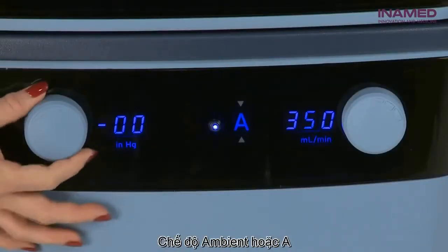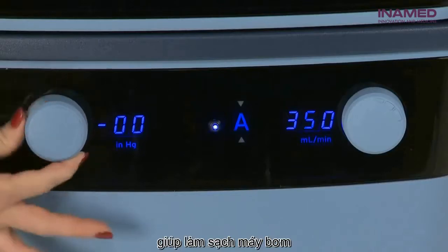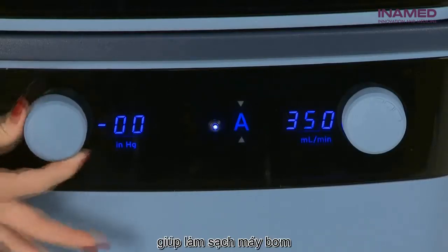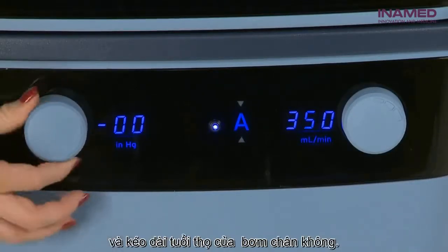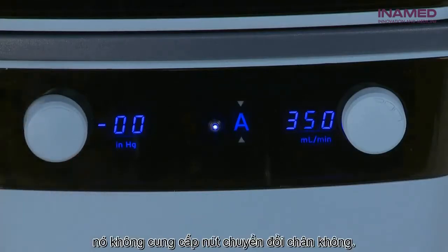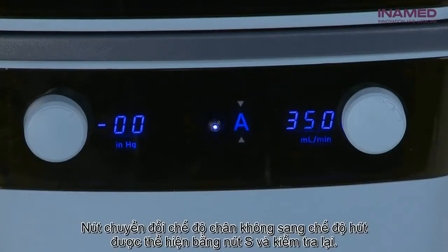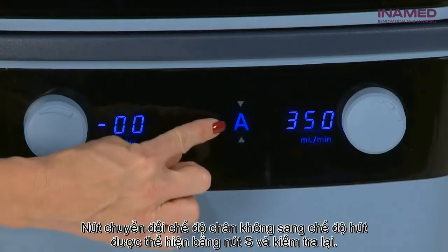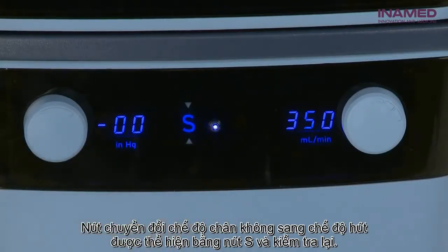The ambient mode, or A, acts like a vent, which clears the pump of condensation and greatly extends the life of the vacuum pump. It does not provide vacuum. Toggle the vacuum mode button to engage the suction mode indicated by the letter S and retest.